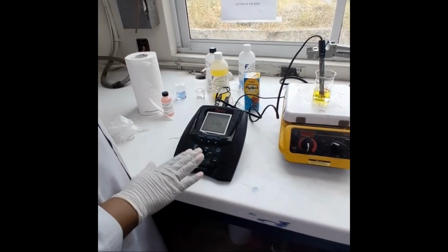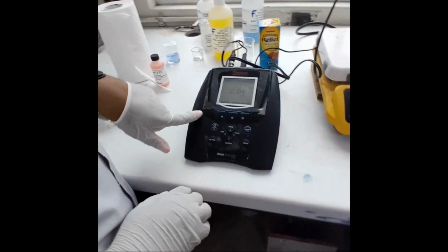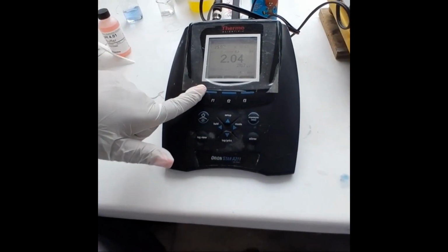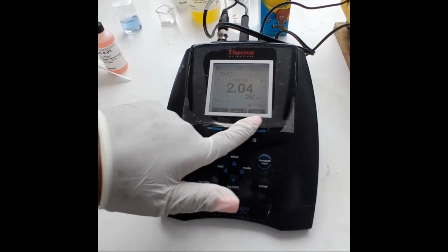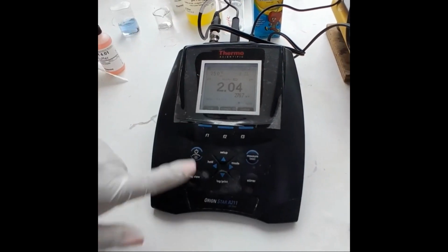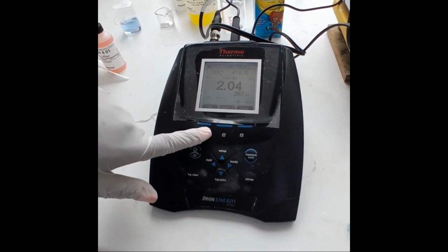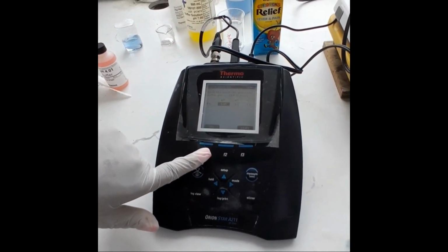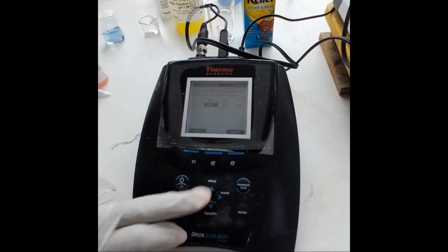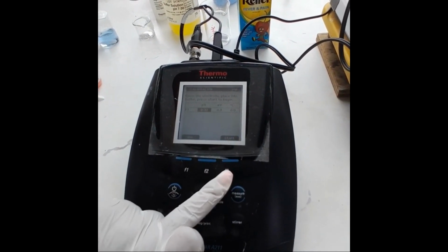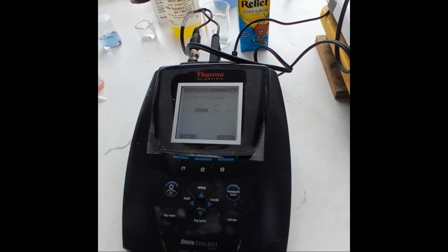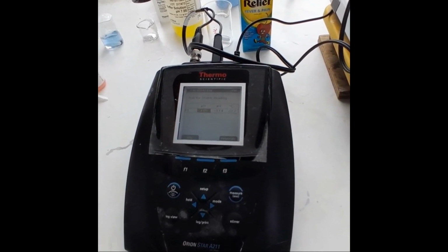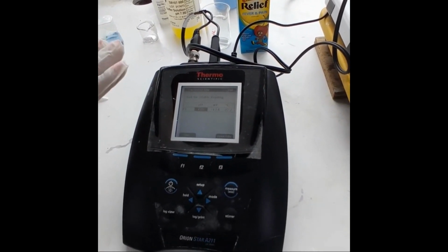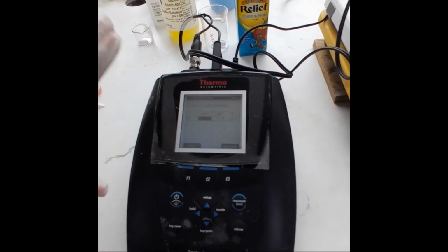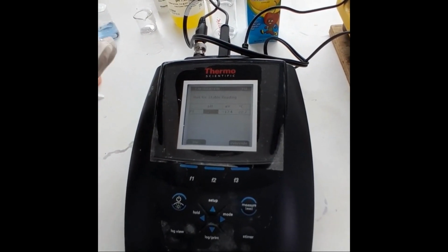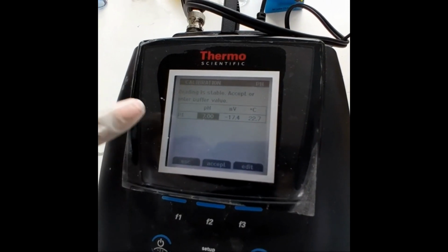Next, we would come here and press calibrate. If you look on the screen, you can see calibrate, sample ID, and setup. So we're going to click F1 underneath calibrate. All right, so now that it's in pH buffer 7, we will press F3 for start. And while we start, we'll wait until the pH meter stabilizes and the reading is ready. So now we can see it has stabilized.